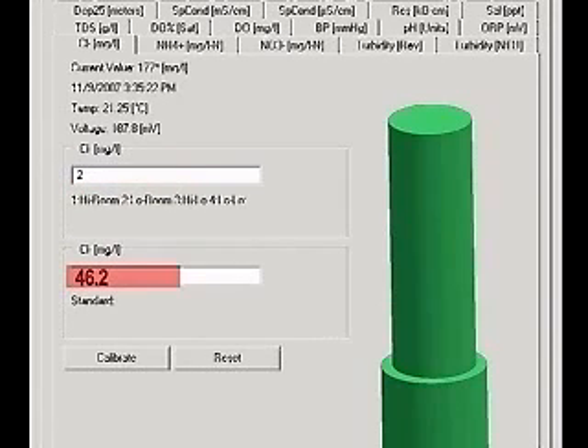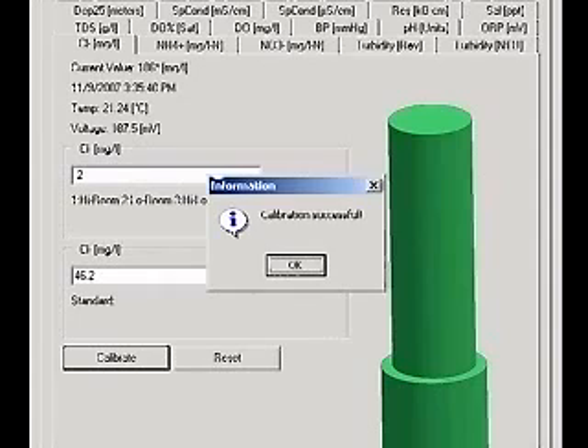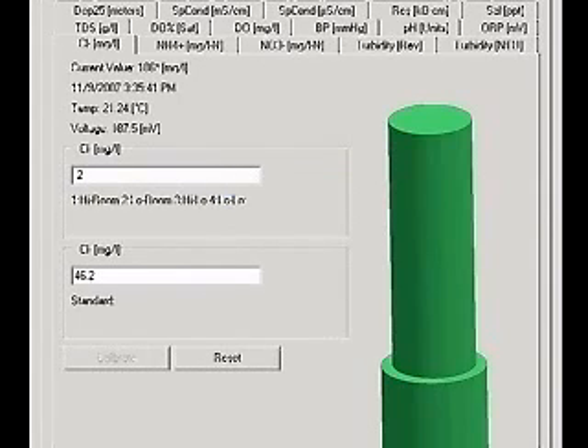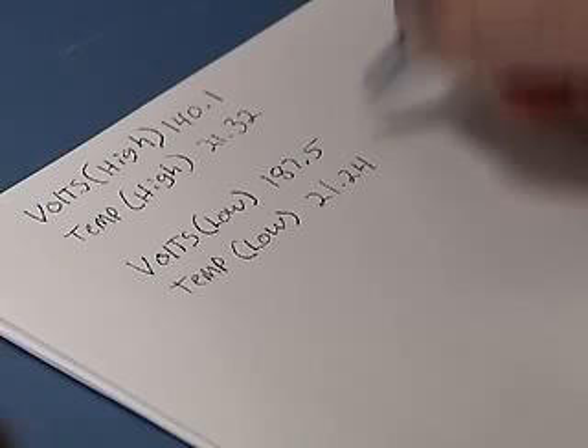Type 46.2 into the second box and click Calibrate. A calibration successful message will appear. Record the temperature and the voltage reading. The two temperatures must be within 0.5 degrees centigrade of each other for a valid calibration.